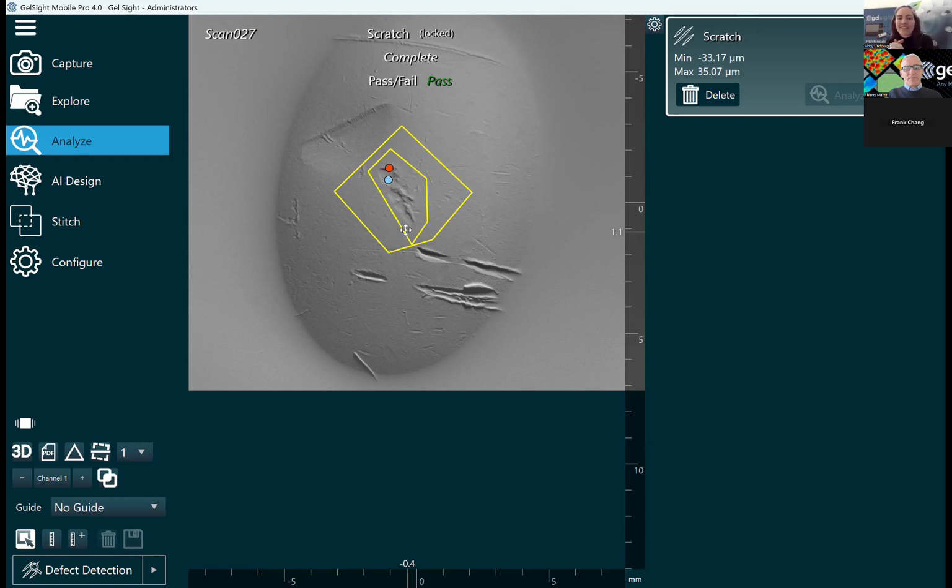Using the defect detection function for a smaller radius, for example, measuring numerous defects in small diameter tubing. So one of the things with the defect detection function is that it's really for flat surfaces or large radii. I'm not going to talk about it in detail today, but we do have our pit detection function, which might be a better fit for this one.